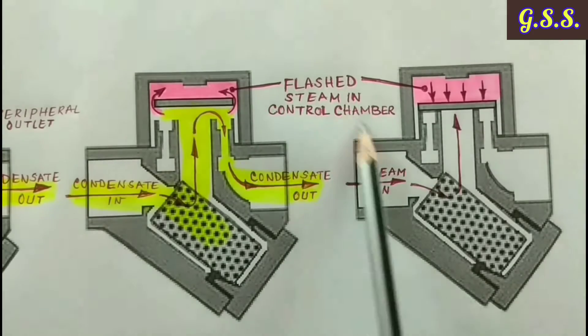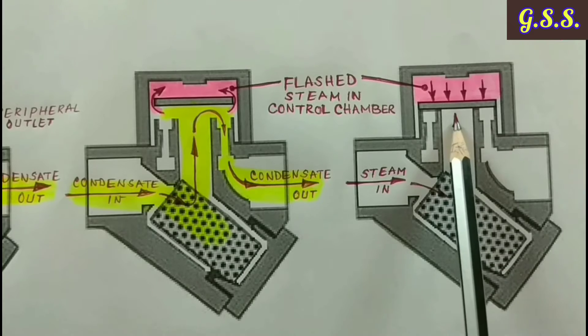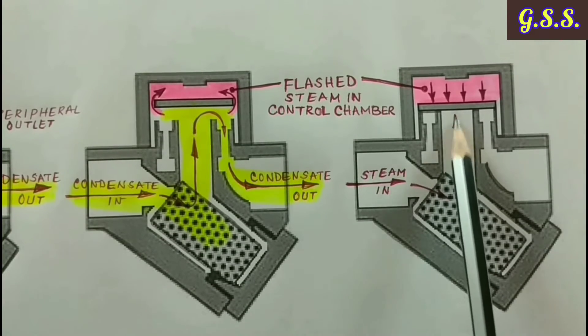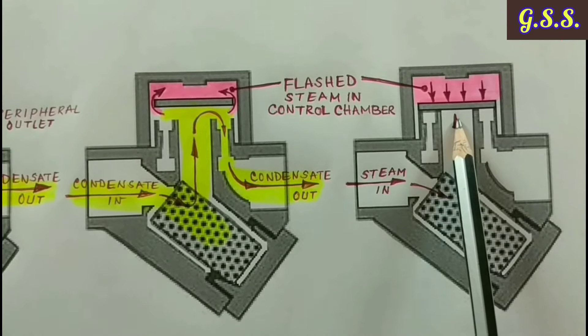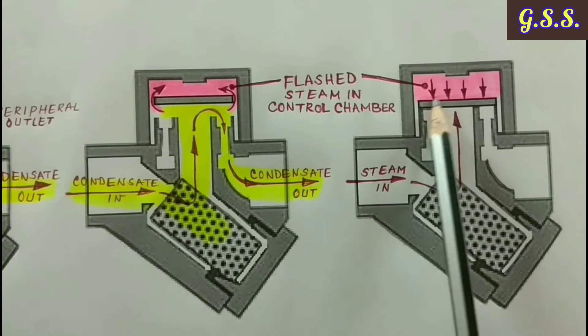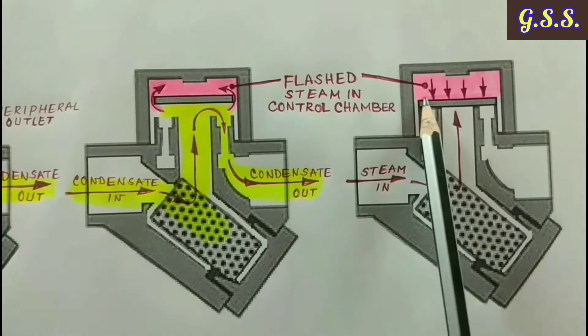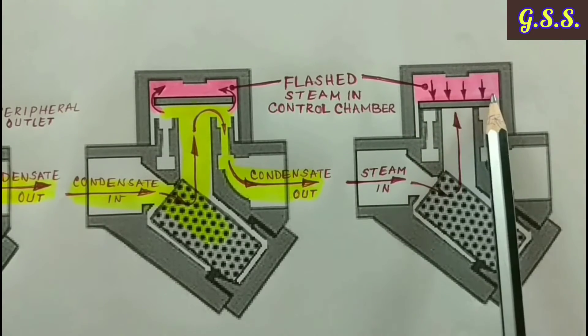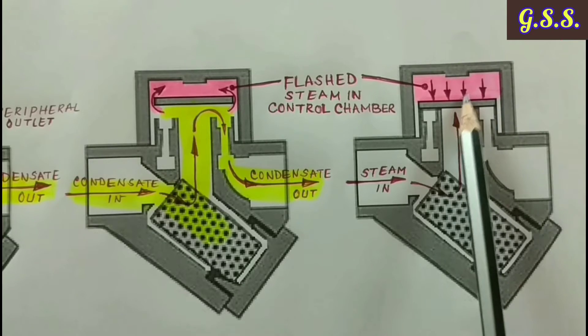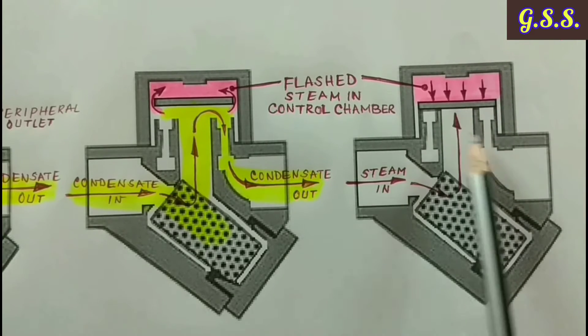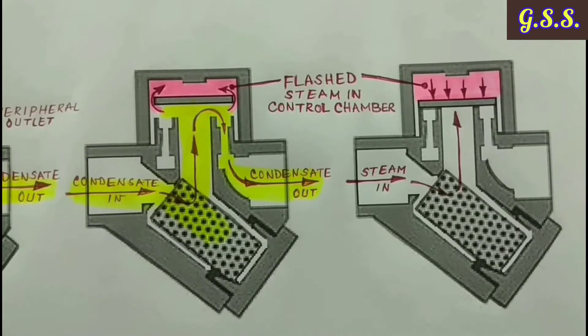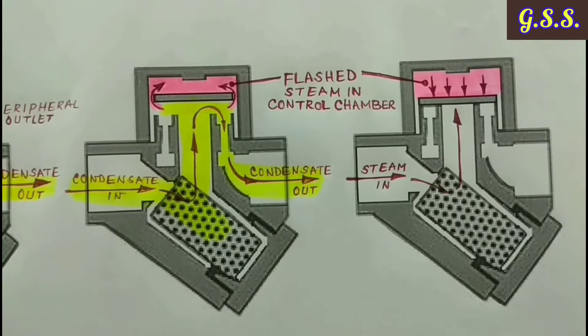In this condition, the upward force on the disc equals the inlet area multiplied by the incoming pressure of steam or condensate. The downward force on the disc equals the flash steam pressure in the control chamber multiplied by the disc top area. Since the disc top area is much greater than the inlet area, the downward force becomes higher, which pushes the disc down and the flow path is closed.